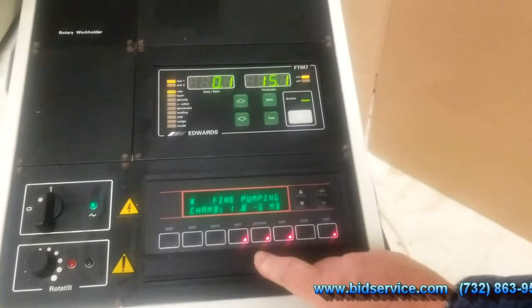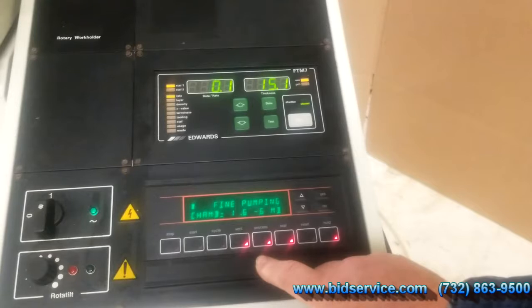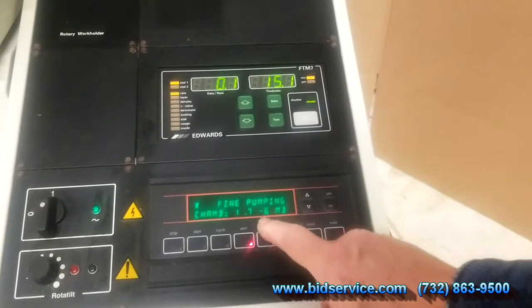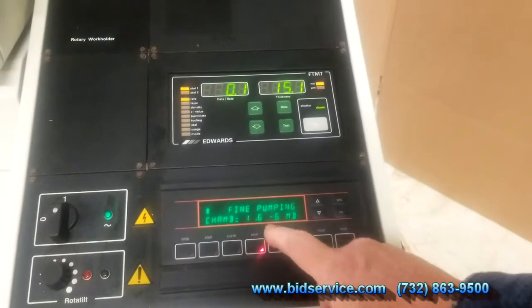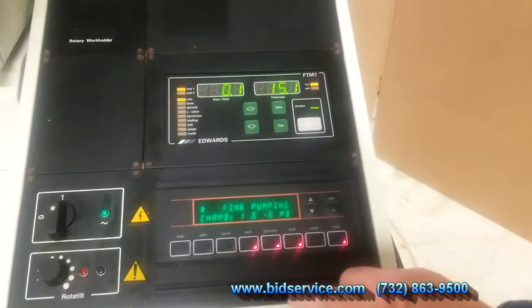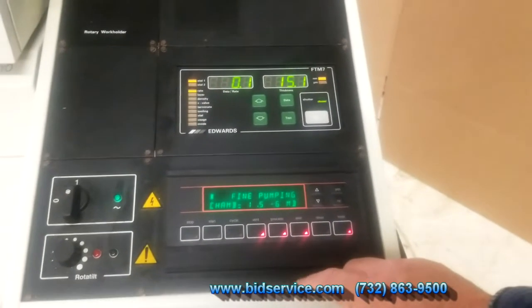Basically it's your auto pump down controller, with your vacuum gauge and everything. As you can see, the chamber right now is at 1.5 times 10 to the -6, without any LN2 and with a diffusion pump system.